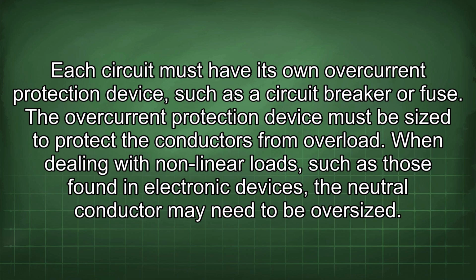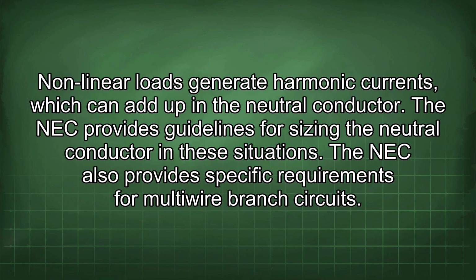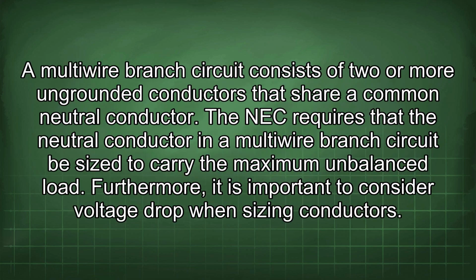When dealing with nonlinear loads, such as those found in electronic devices, the neutral conductor may need to be oversized. Nonlinear loads generate harmonic currents, which can add up in the neutral conductor. The NEC provides guidelines for sizing the neutral conductor in these situations. The NEC also provides specific requirements for multi-wire branch circuits. A multi-wire branch circuit consists of 2 or more ungrounded conductors that share a common neutral conductor. The NEC requires that the neutral conductor in a multi-wire branch circuit be sized to carry the maximum unbalanced load.